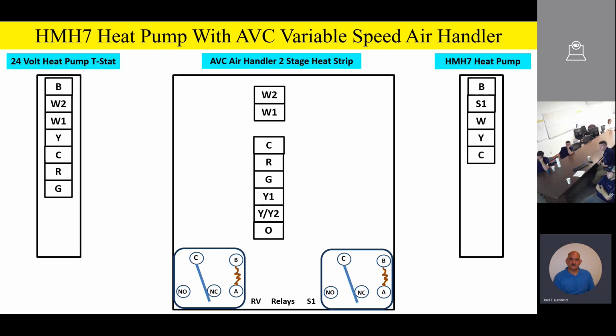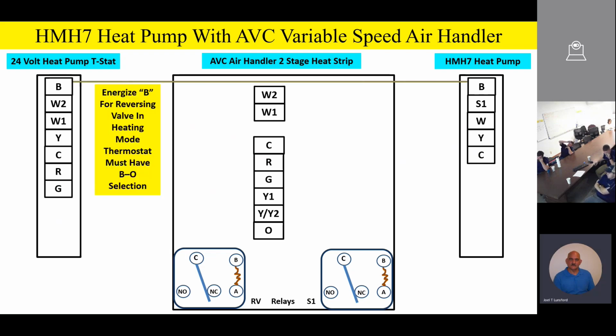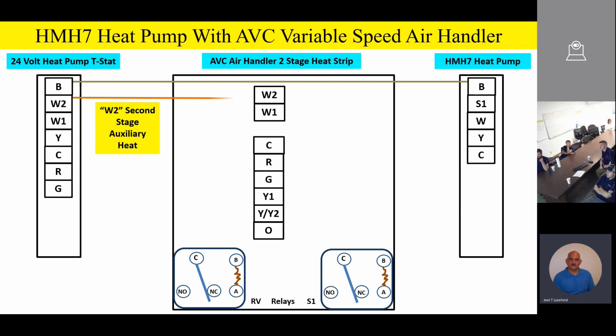And we have a 2-stage heat strip in this air handler. Now, please remember the air handlers do have pigtail connections, but we're just showing them on the block diagram so it's easy to look at. So B terminal, just like before, goes to B outside. That's going to be our reversing valve for heating in the heating mode of operation. W2 is our 2nd stage auxiliary heat.